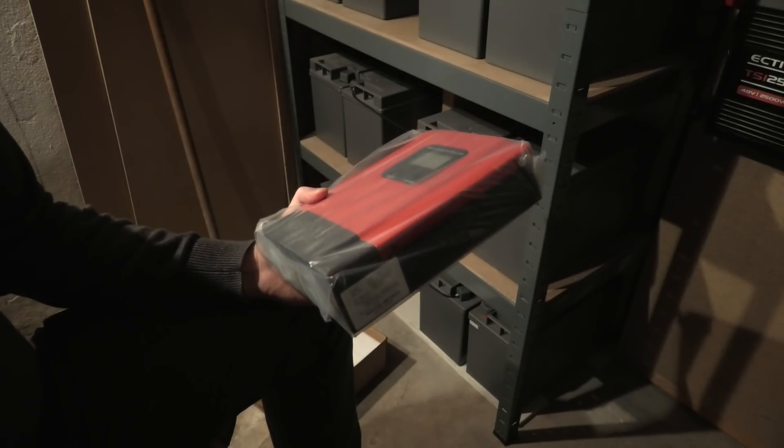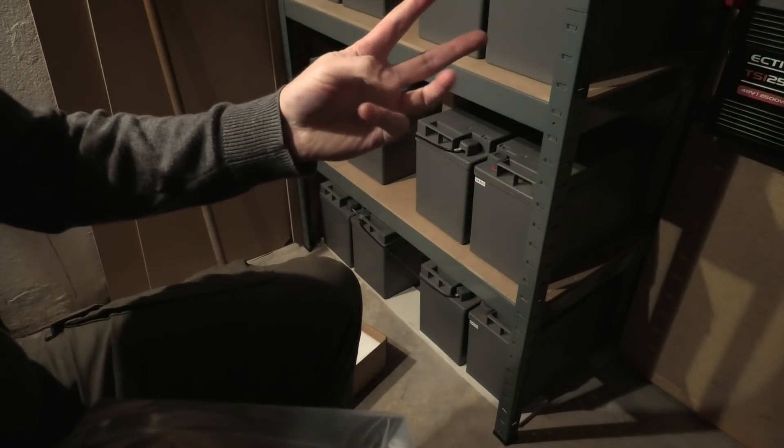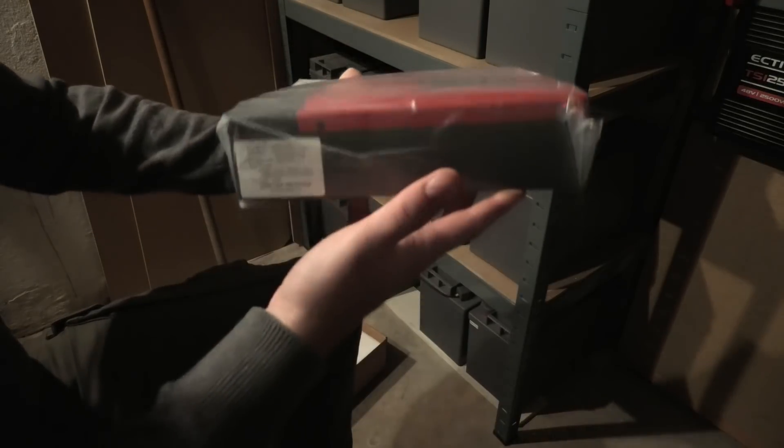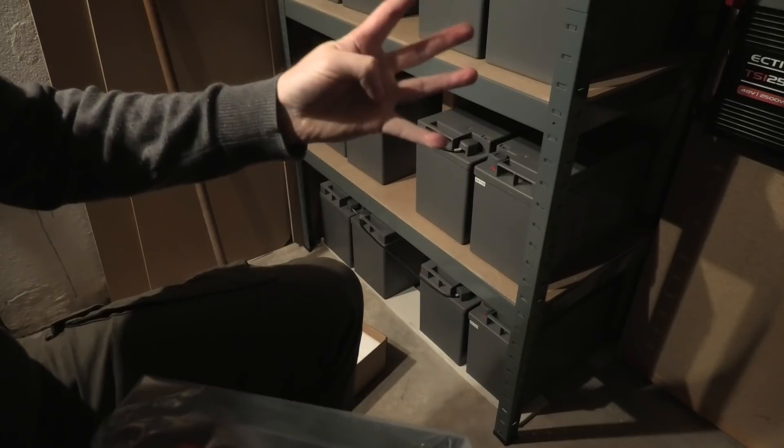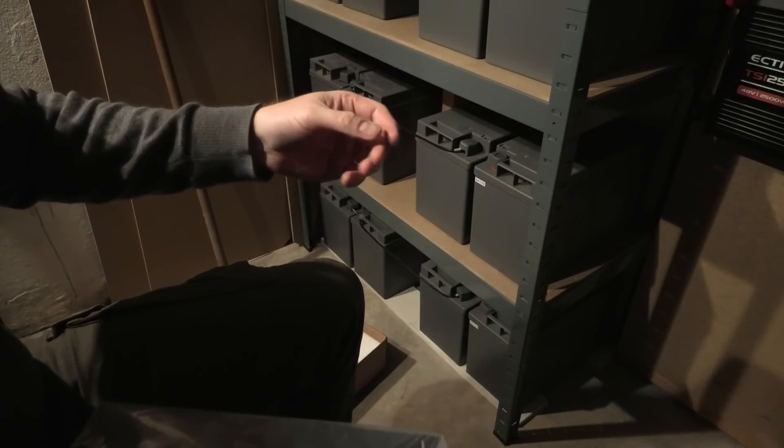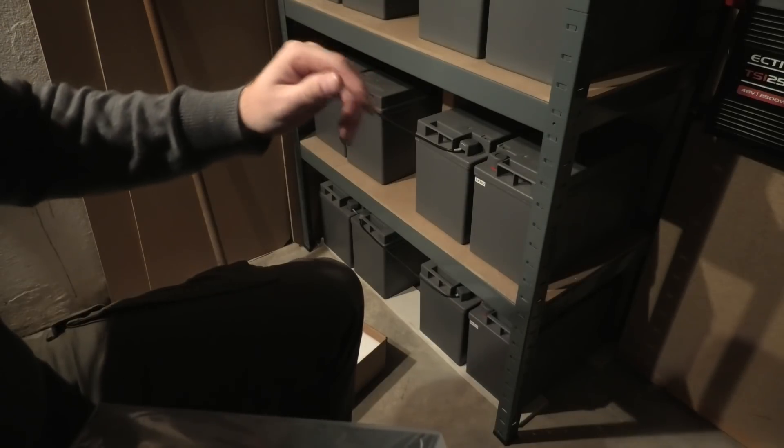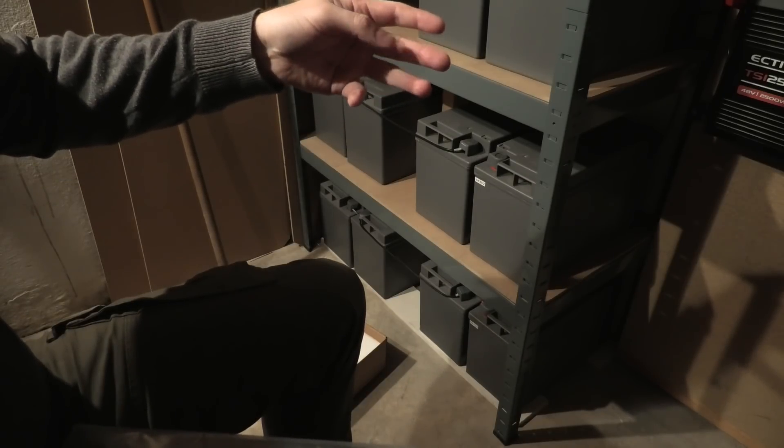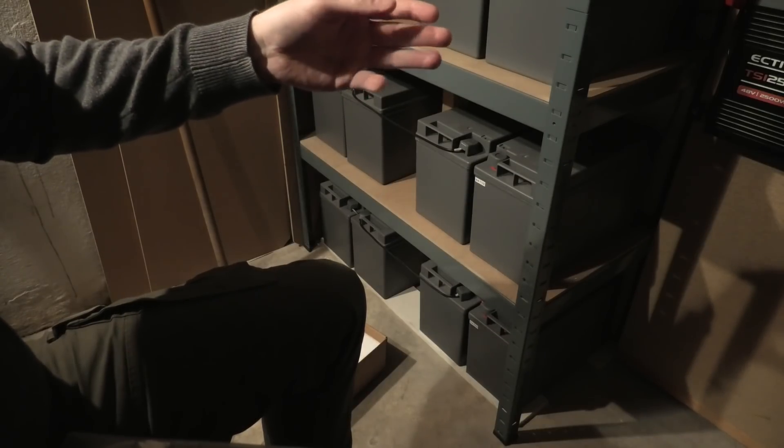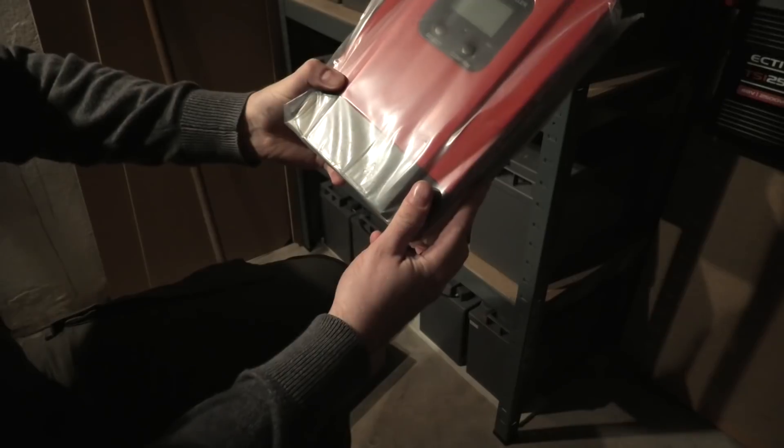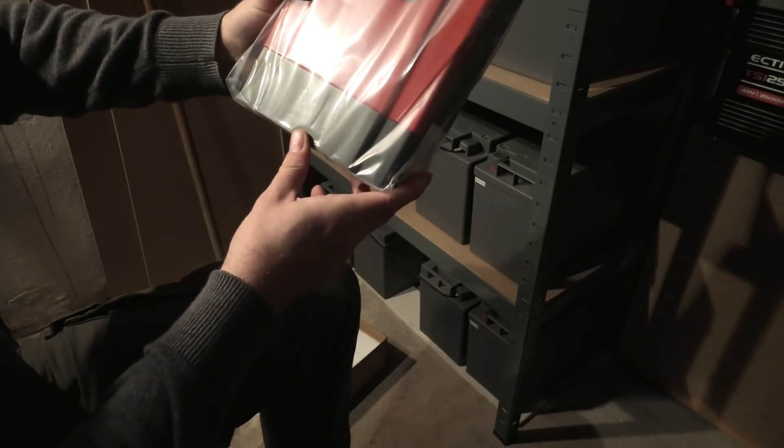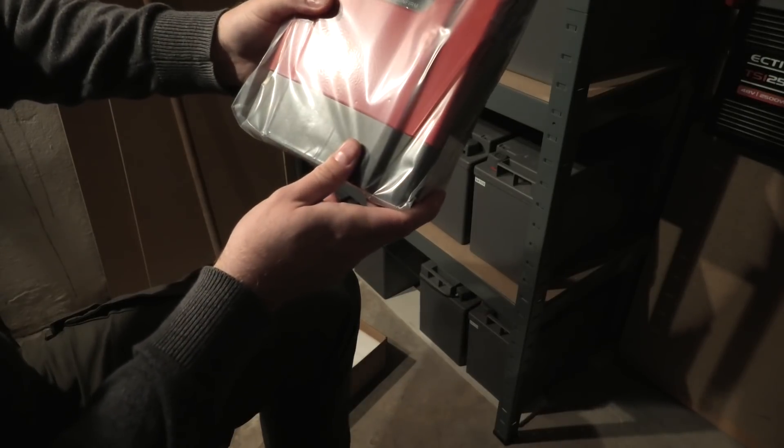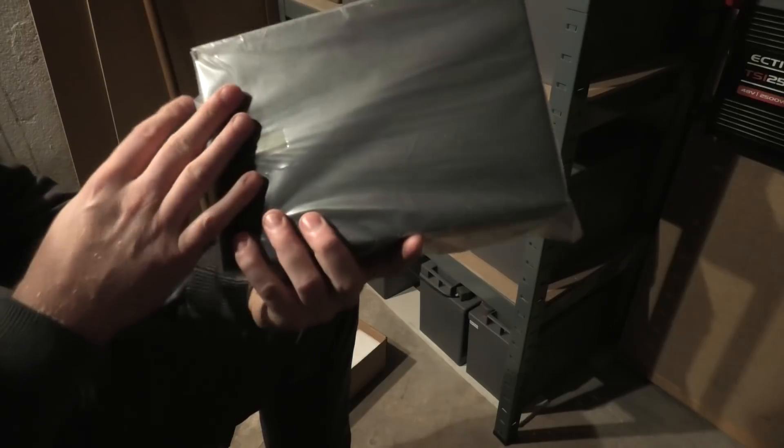This one also had a better maximum PV max voltage, which is the power from the solar panels. The other one that didn't work with the cloud was only 130 volts. This one is 150 volts, and I'm actually battling with myself if I should reconfigure my solar panels. Right now I have four strings of three panels, and now that it can do 150 volts, I believe I could do three strings of four panels, and that would give me a better result. There are losses in the wires when you transfer DC power. The higher the voltage and the lower the current, the better. With more panels in series, they will actually be able to produce power for the charge controller longer.